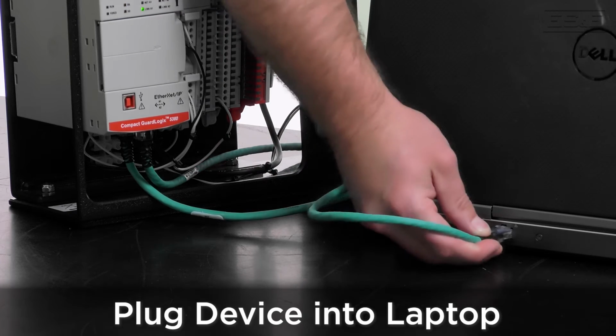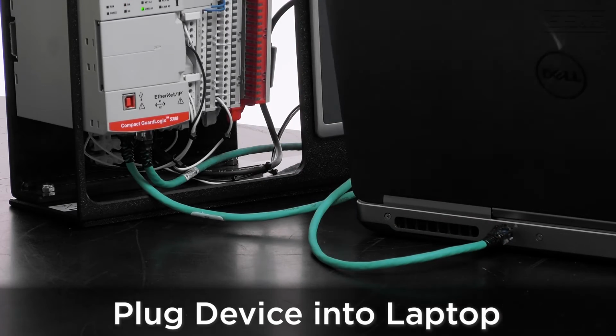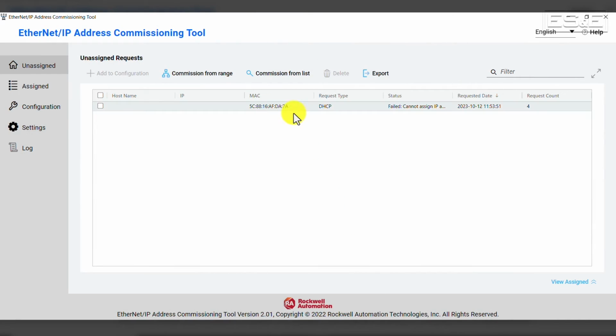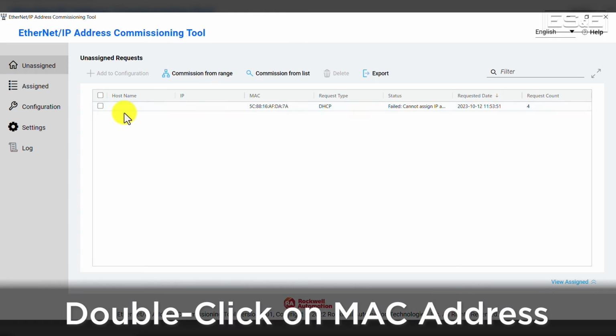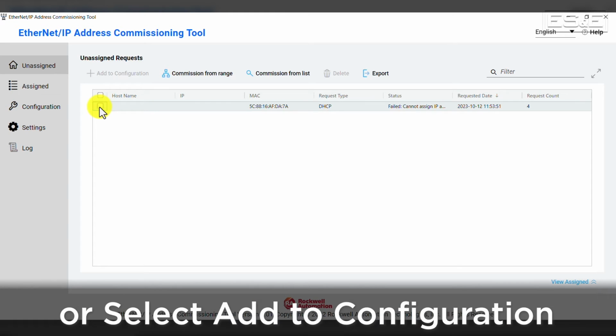Then we want to plug our device into the computer. If we plug our device into the computer and do not see its MAC address appear, then a helpful tip to force the DHCP request would be to put your computer back to DHCP and wait for the MAC address to appear. Once the MAC address appears in the unassigned tab, you can double-click on the MAC address or select the Add to Configuration button.